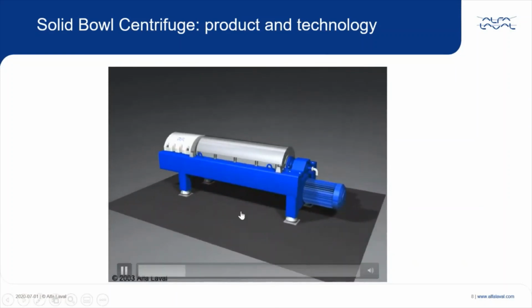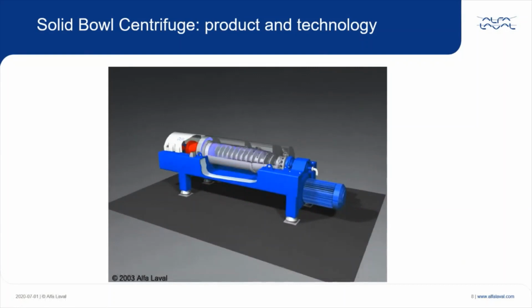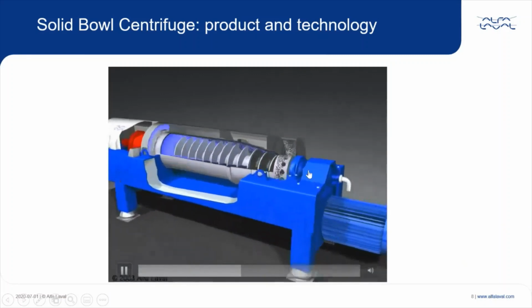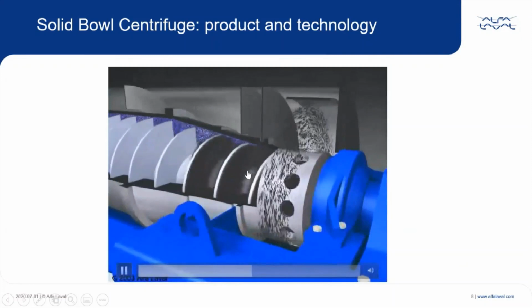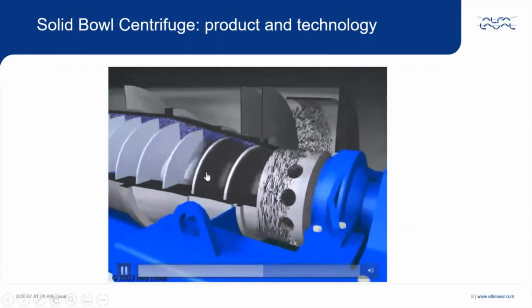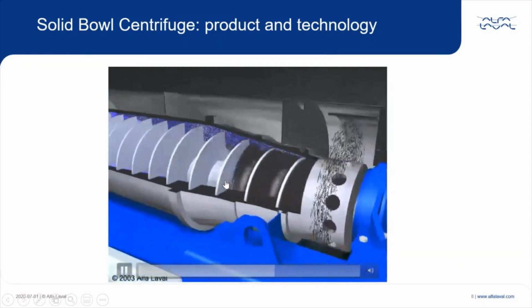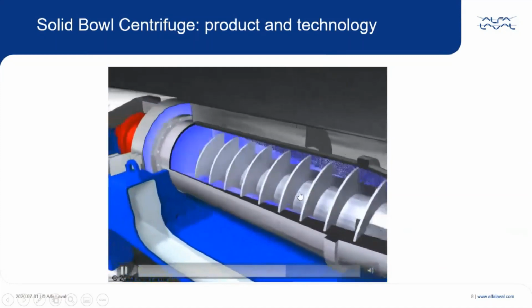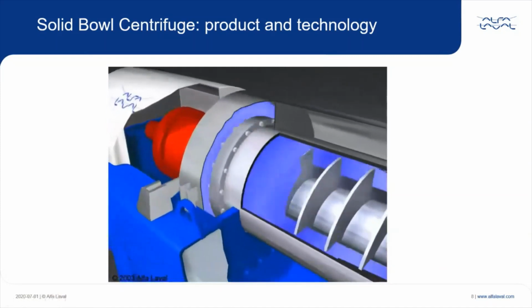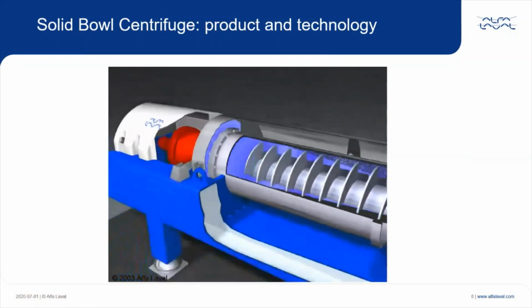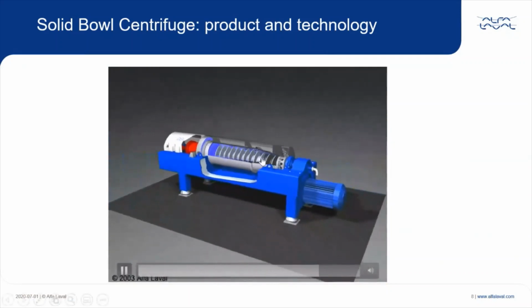So here's the animation. You can see the feed tube in white color on the right side, and we have removed the casing to show the bowl. Now the bowl has been cut to show the screw conveyor, which is inside. Through the feed tube, the feed enters into the centrifuge. The conveyor shaft is hollow, allowing the feed tube to enter through it. And the slurry then enters into the centrifuge through openings in the conveyor shaft. We call those windows.